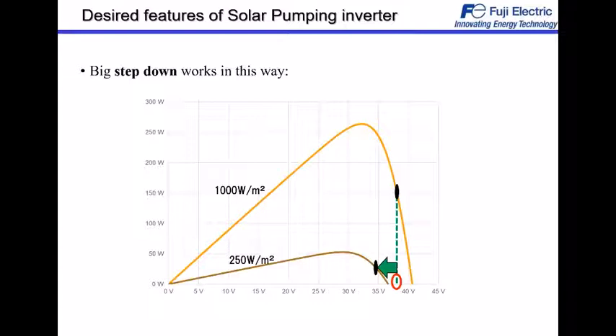Instead of stopping, it moves to another point, reducing the speed of the pump. Of course, we can set a minimum speed, but it tries, above this minimum, to search for a point where it can still drive the pump. That's what the drive is doing.